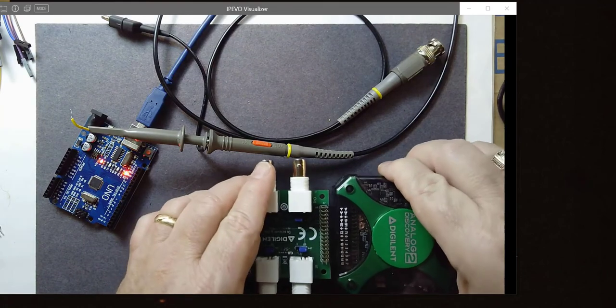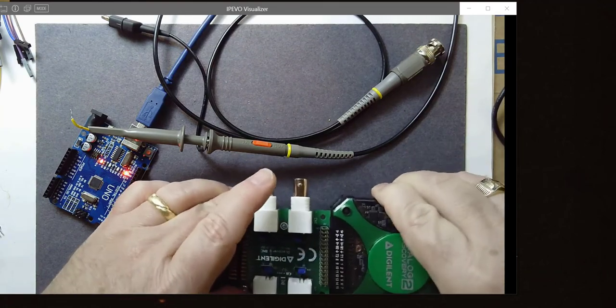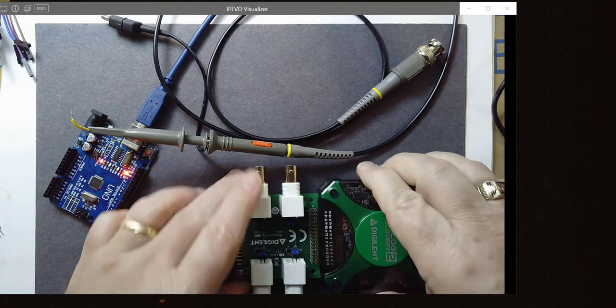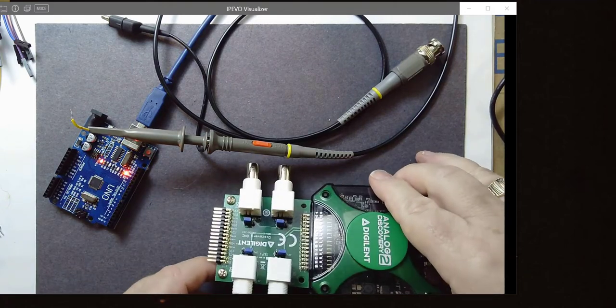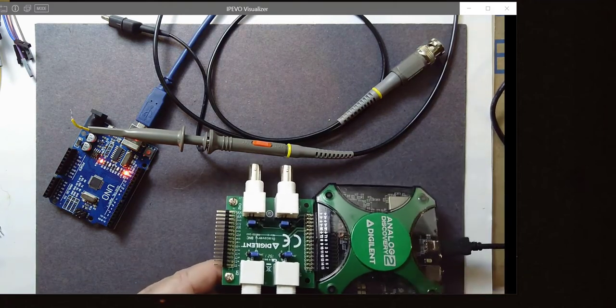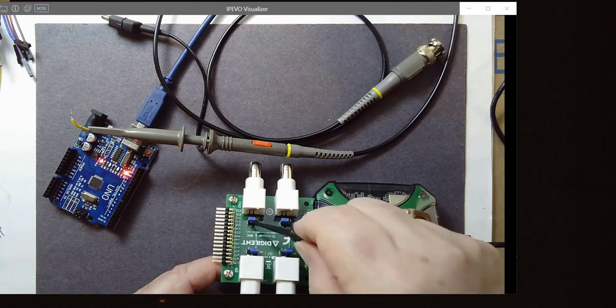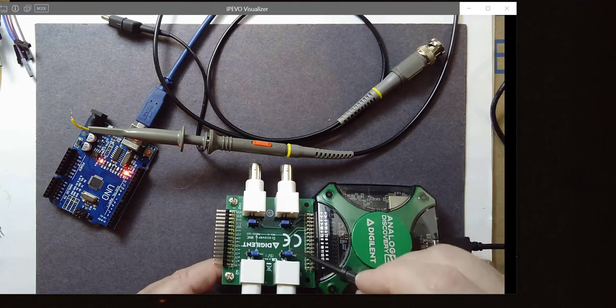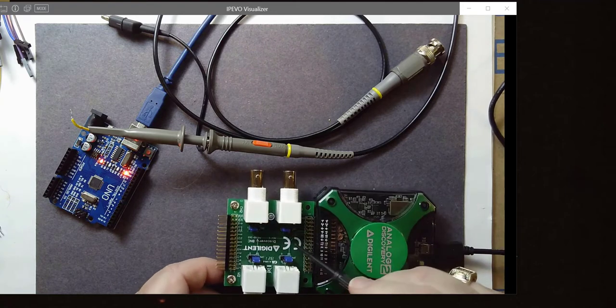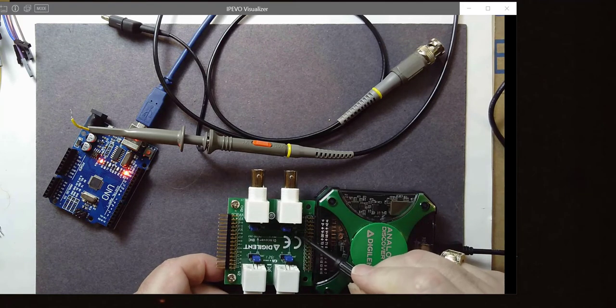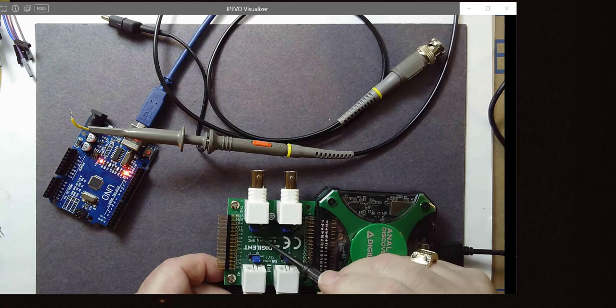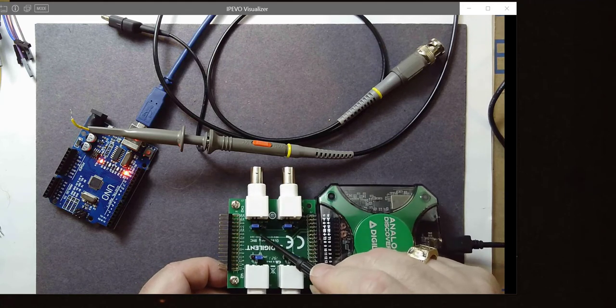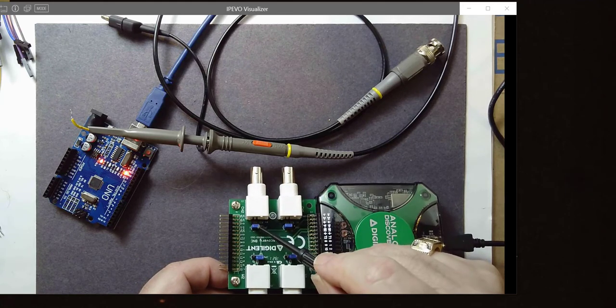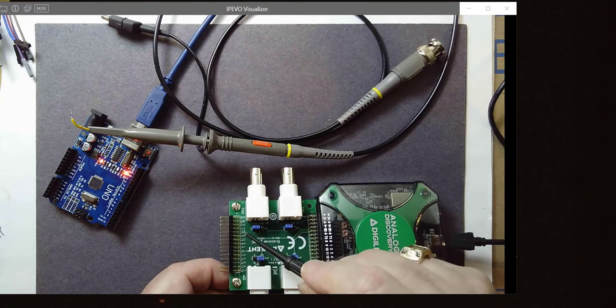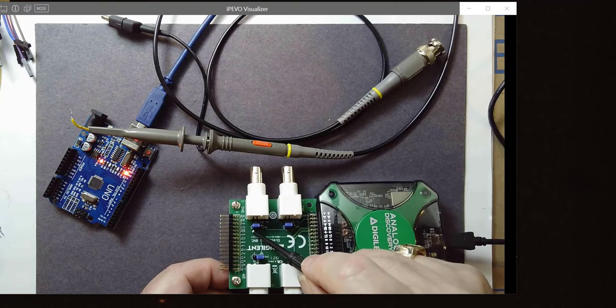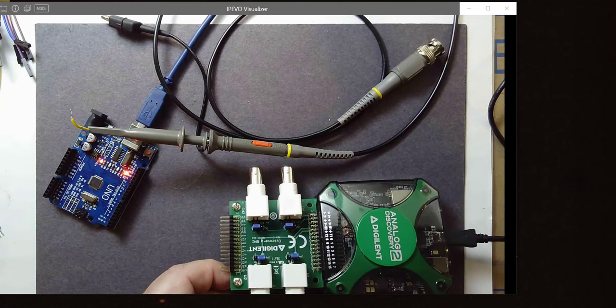So we're going to slip in the BNC adapter, and there are two important things to pay attention to when we look at the BNC adapter. The first is that we have these flags sticking off here. And these flags are really important because they come from the factory set for AC coupling. We want to use them in DC coupling. And so you have to read very closely, move the blue flag all the way over to the left side in this orientation so that it's connected to DC. And I've done that for both channels.